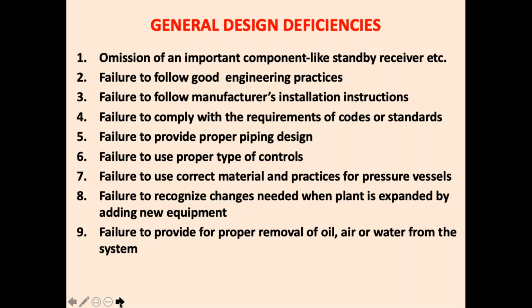Then failure to follow good engineering practices and correct standards, failure to follow the manufacturer's installation instructions, failure to comply with requirements of codes and standards, failure to provide proper piping design. Now, for the piping design, only a P&ID is not good enough. You need to give 3D drawings showing how the piping routing should be done. That is very, very important.